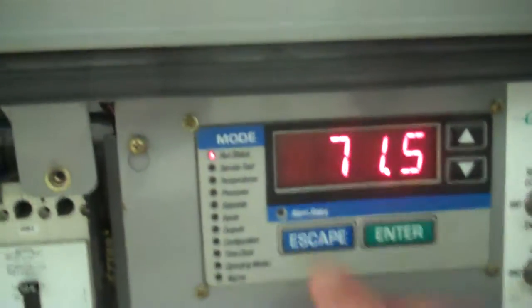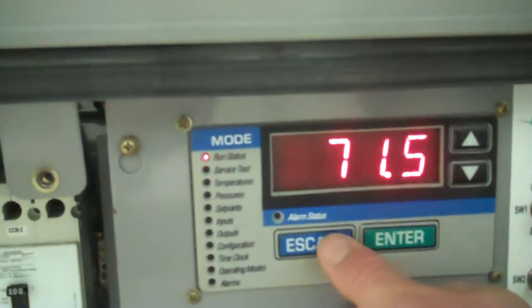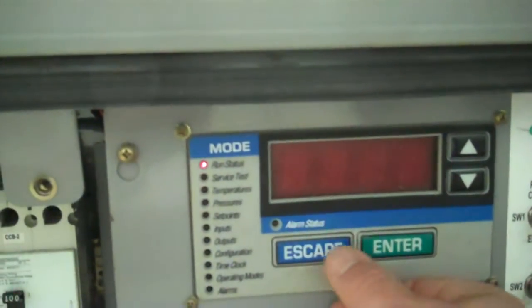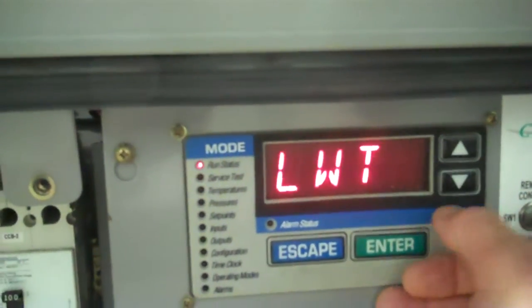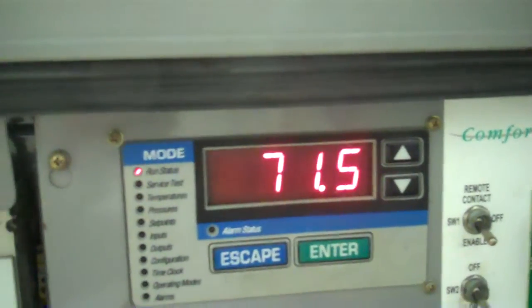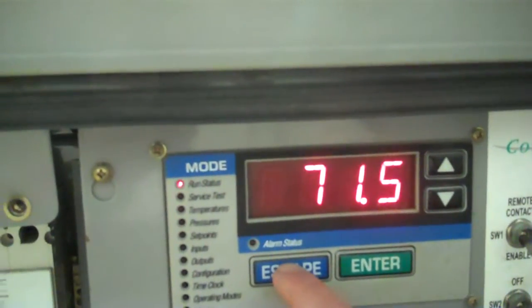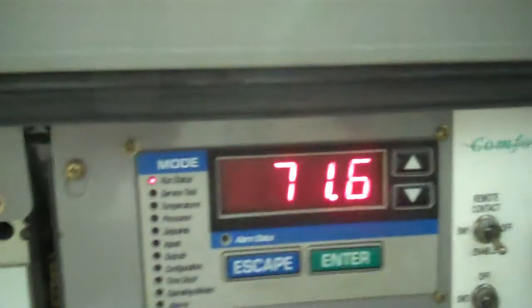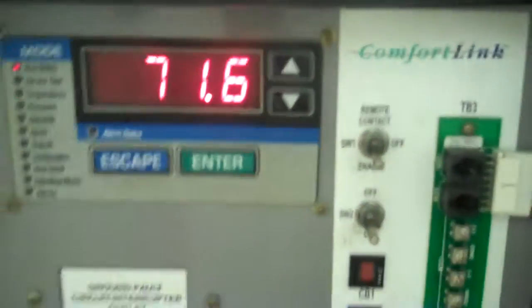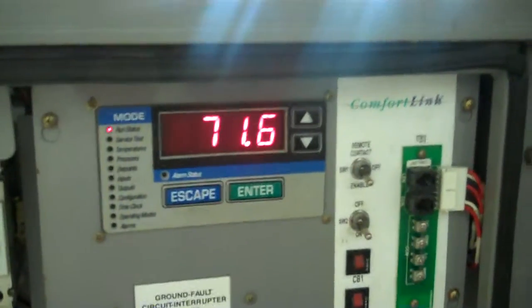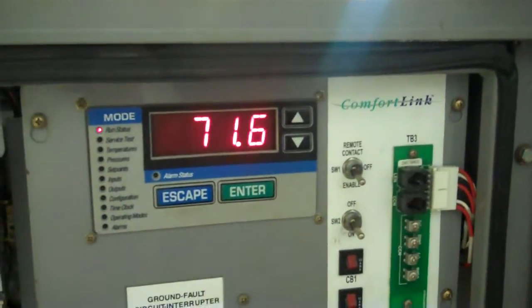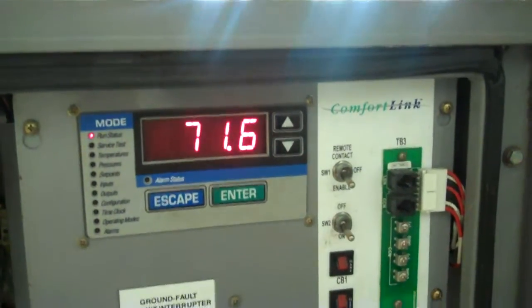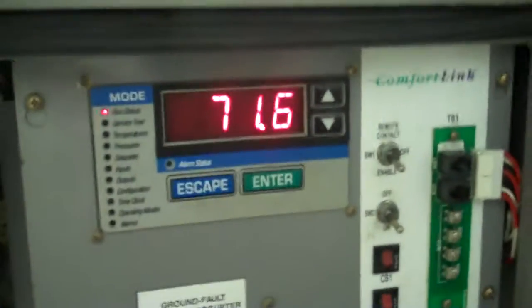EWT is entering water temperature. Leaving water temperature should be right about the same. Once we start chilling here, once it turns on and we're underway, we'll compare the entering water temperature and the leaving water temperature. That is effectively your delta T over the exchanger.